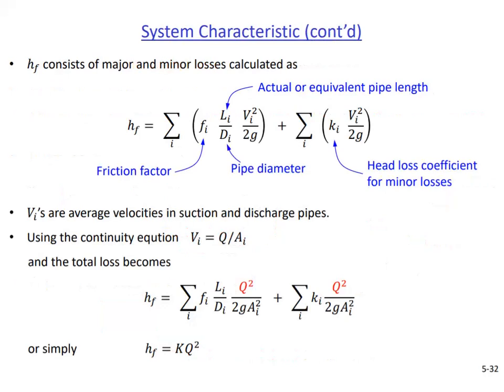The flow rate dependency of the system characteristic comes from the head loss, which can be written as the sum of major and minor losses. Suction and discharge pipes of the system create major loss, and all other piping elements such as inlets, outlets, valves, bends, junctions, cross-sectional area changes, etc. create minor losses. After relating the velocity in different parts of the piping system to the flow rate, all other details can be combined into a single parameter shown here as K, resulting in this final head loss equation. Each system has its own K value. As you see, for a given K, the head loss increases with the square of the flow rate. Faster flow experiences more loss.